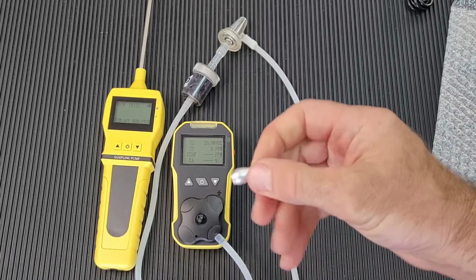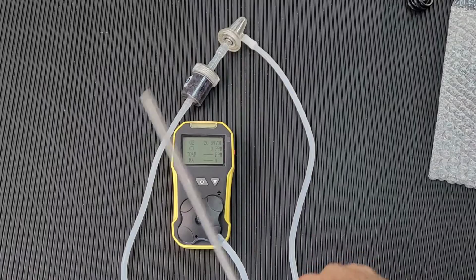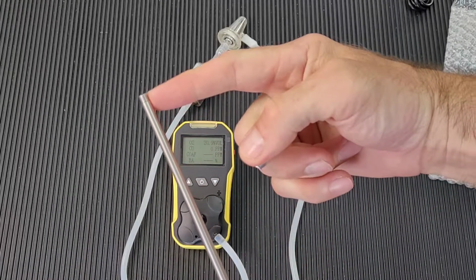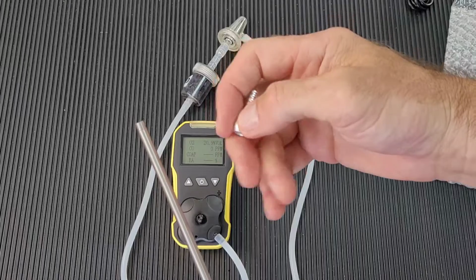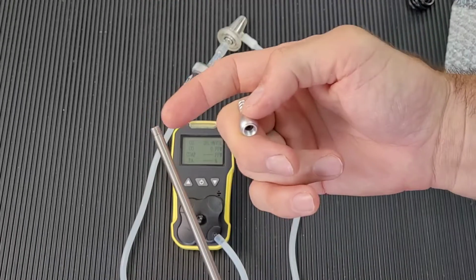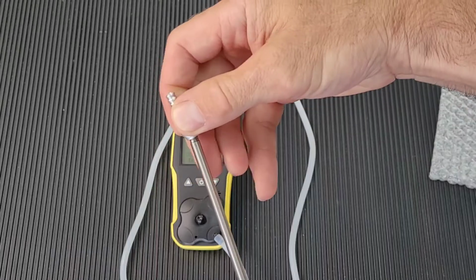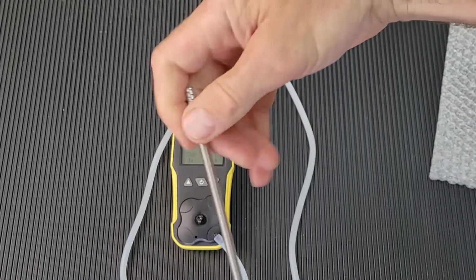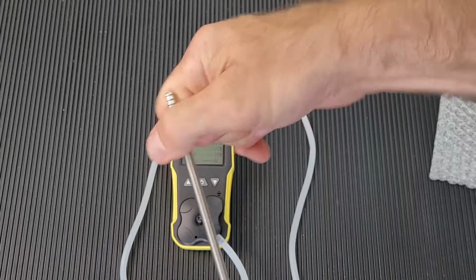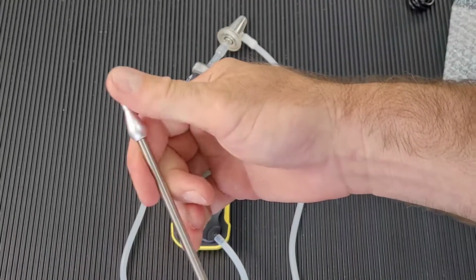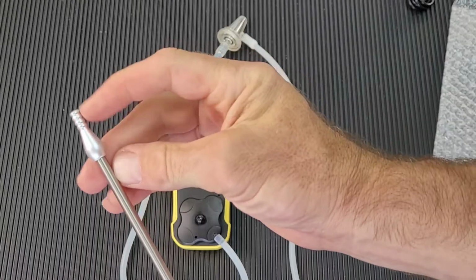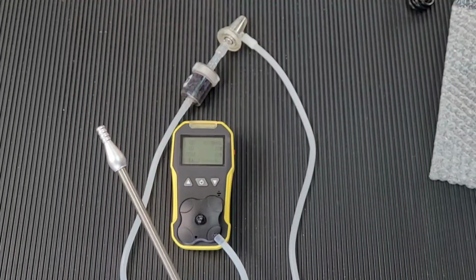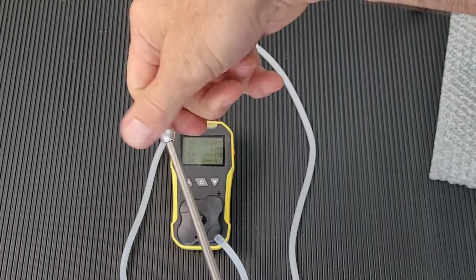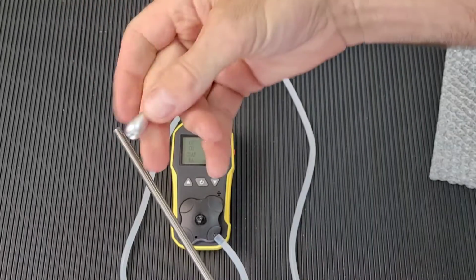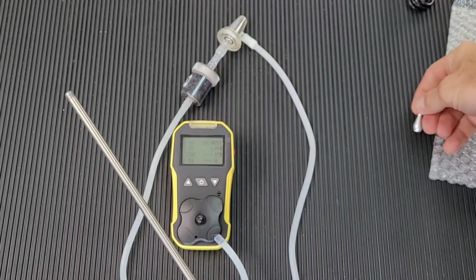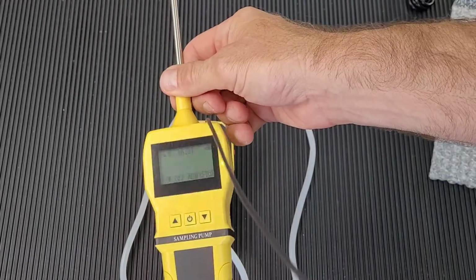And then people usually say, "What's this, Dr. Cos?" Well, this fits on the end of the stainless steel probe. So if you're going to undertake a combustion analysis, usually we drill a hole into the B-type flue, but in this case you don't need it. This is only used for ambient measurements, so you're not worrying about the end cutting someone or doing anything that is harmful. In addition, this tip serves as a barb, so you could put another tube onto that to extend, or to put another little probe. So that's why we have this nipple over here. Not many people need it for combustion analysis, but we do put it in there just for your requirements, if required.